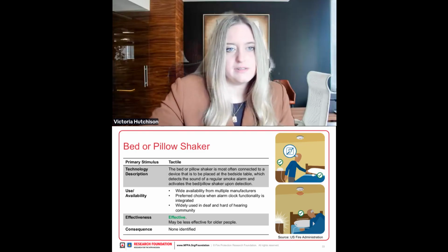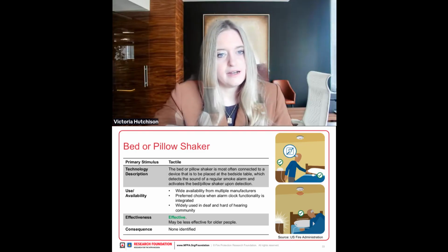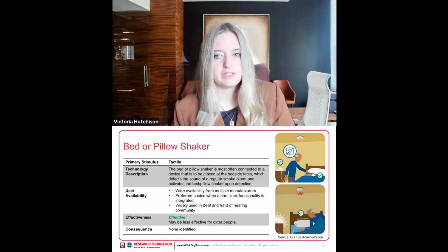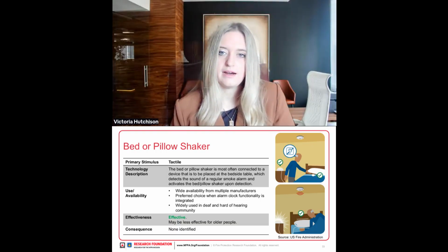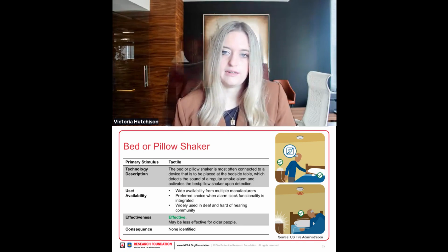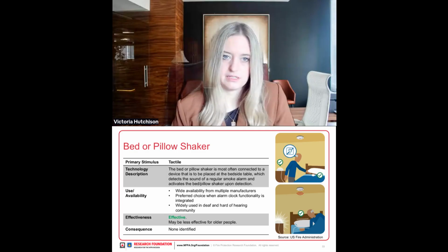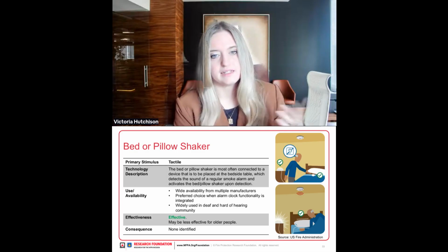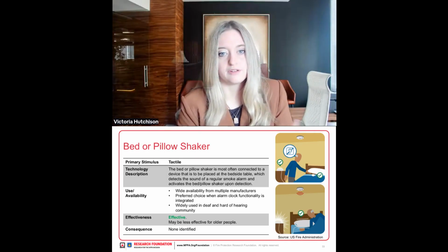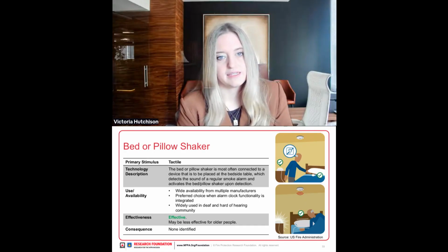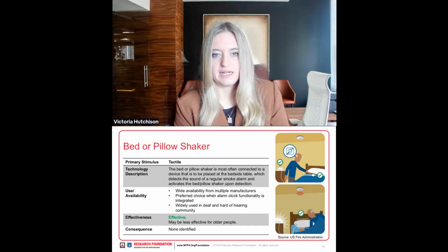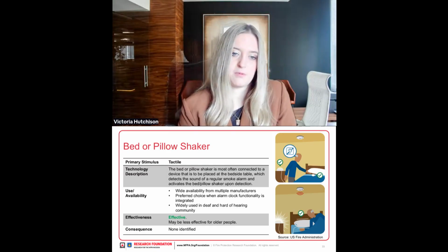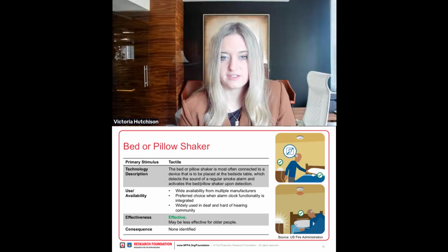So, moving on to bed or pillow shakers. This is something that has really gained a lot of momentum, particularly with the deaf community, as an alternative to a standard alarm. It can be described as a device that's connected to or placed at the bedside table that detects the sound of a regular smoke alarm and activates the bed or pillow shaker upon detection. It does have wide availability from multiple manufacturers.